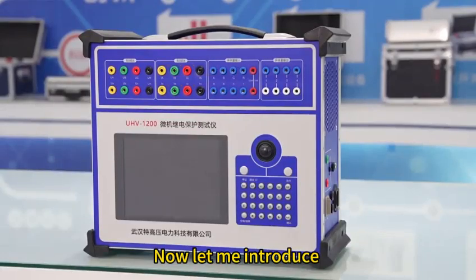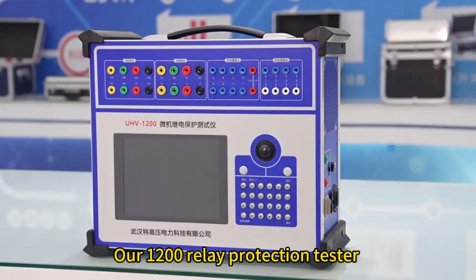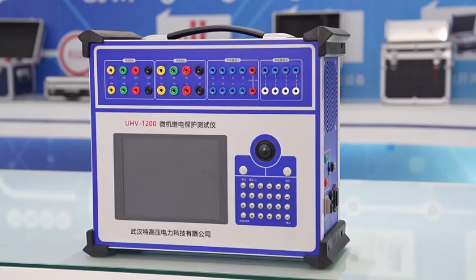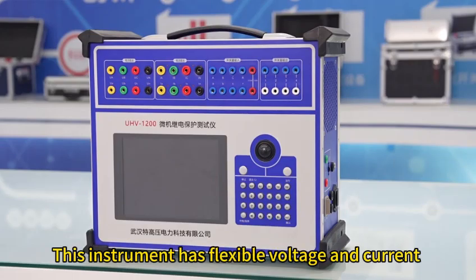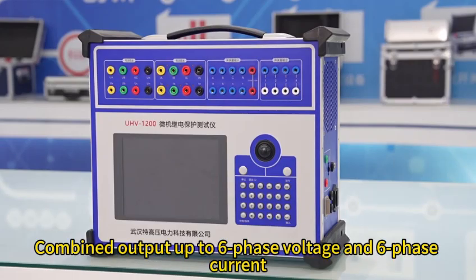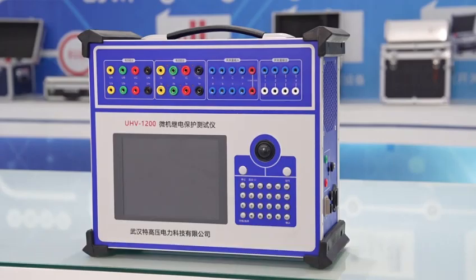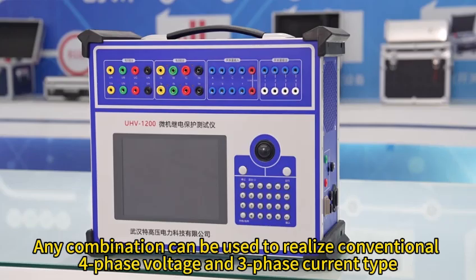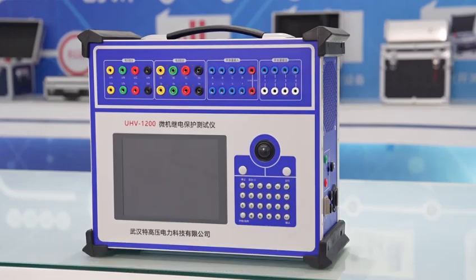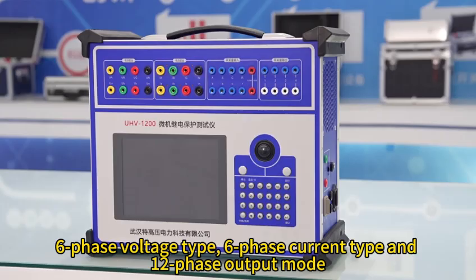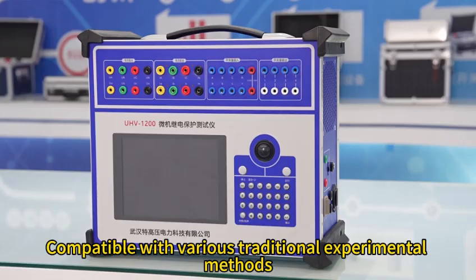Now let me introduce our 1200 relay protection tester. This instrument has flexible voltage and current combined output up to 6-phase voltage and 6-phase current. Any combination can be used to realize conventional 4-phase voltage and 3-phase current type, 6-phase voltage type, 6-phase current type and 12-phase output mode. Compatible with various traditional experimental methods.